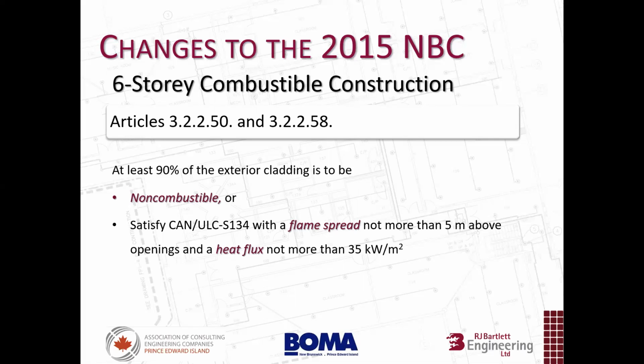combustible cladding. This was recently looked into by a colleague of mine in the office here, and an industry specialist confirmed for us because we did some searching around at the listing guys, the UL Product iQ and things like that. We looked, and there didn't appear to be any listed systems for this, and it's apparent that the criteria identified in this CAN/ULC S134 is actually very onerous and requires the combustible cladding to have been weathered. It's probably an expensive test, and those that appear to maybe meet the performance are just barely passing the performance criteria. So it's my understanding that there's no real listed systems right now that comply with this CAN/ULC S134.